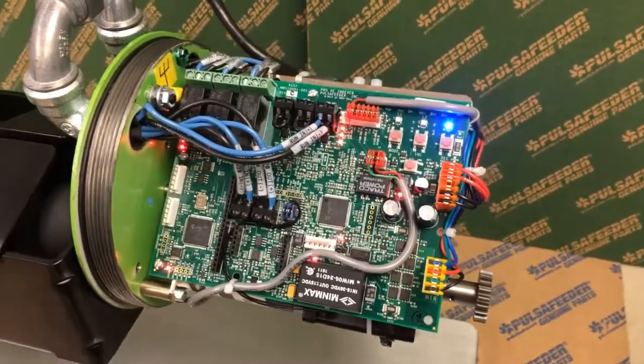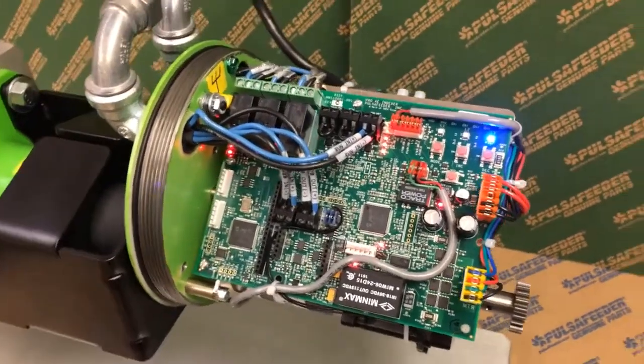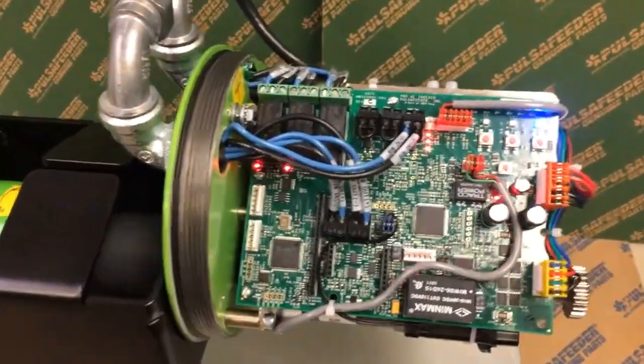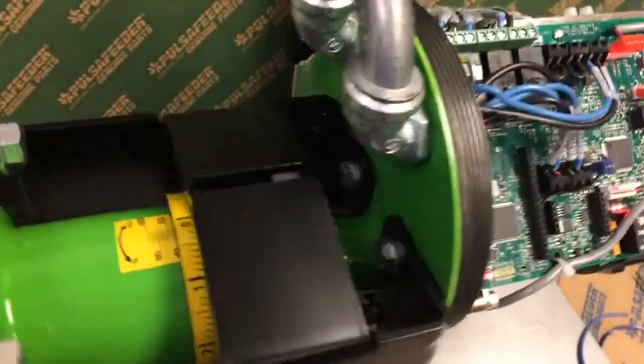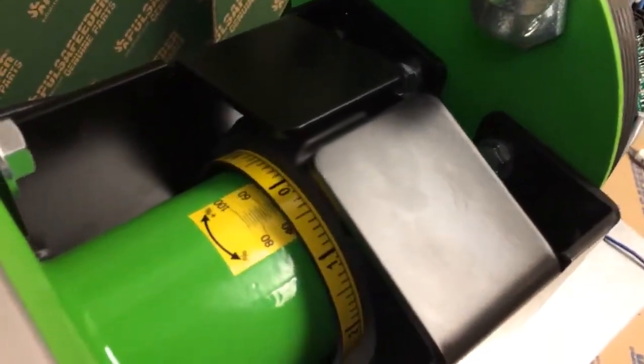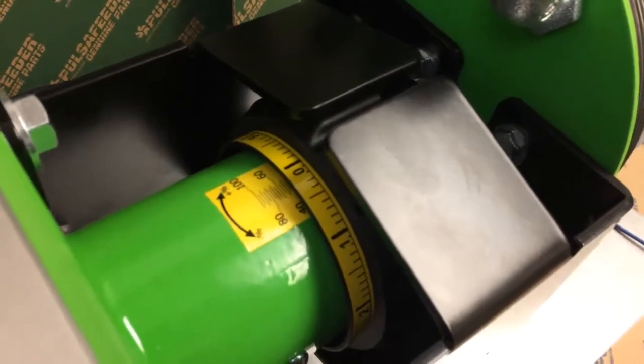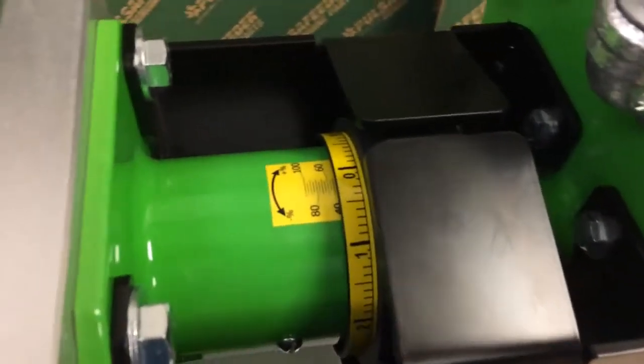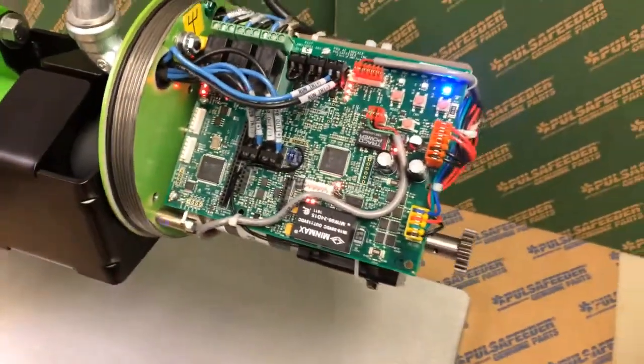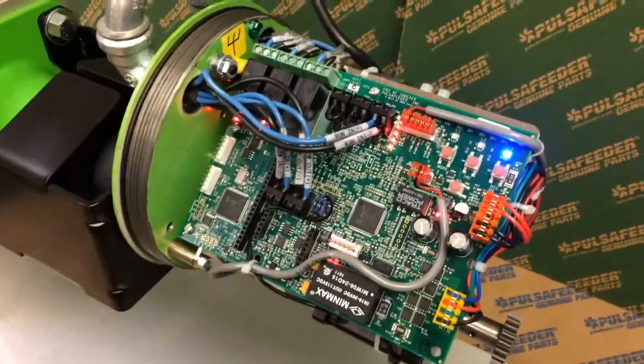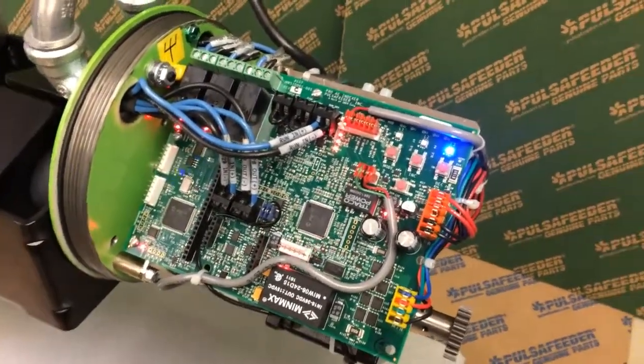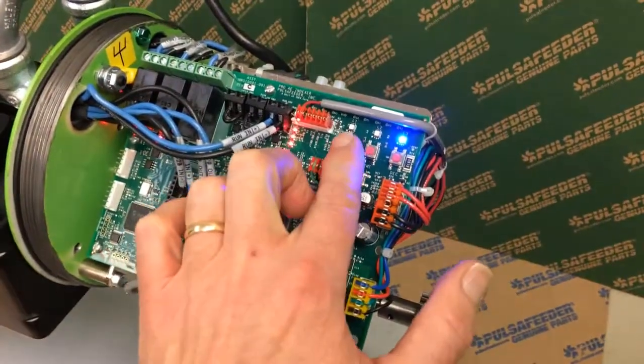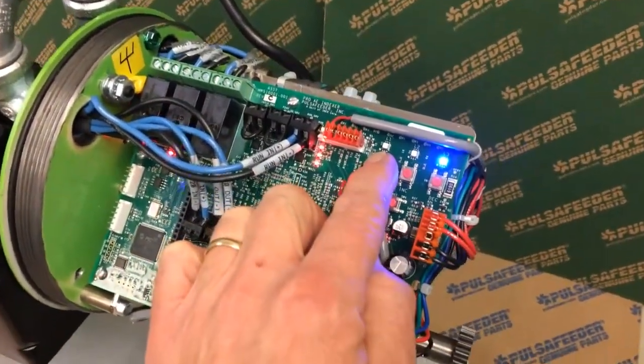Mechanical calibration. Let's talk about mechanical calibration. What mechanical calibration does is it lets the actuator know what the current mechanical setting of the pump is. That's defined by the scale on the pump side, the stroke adjustment mechanism setting, and electrically it lets the actuator know what that setting is. We access that through the standard user interface. It's the third mode button press, so we press that 1, 2, 3 times.